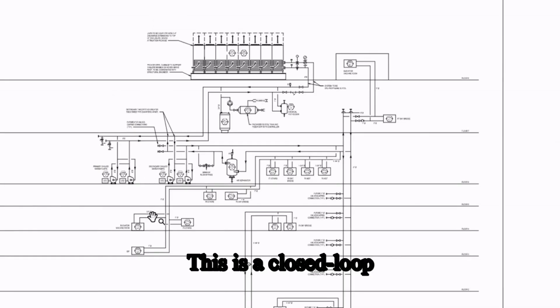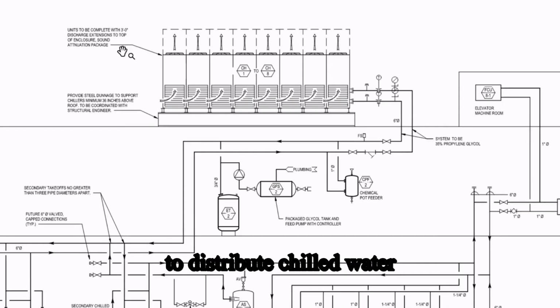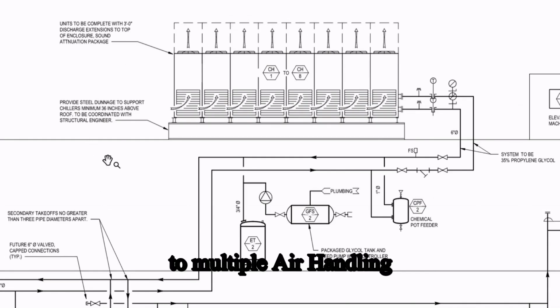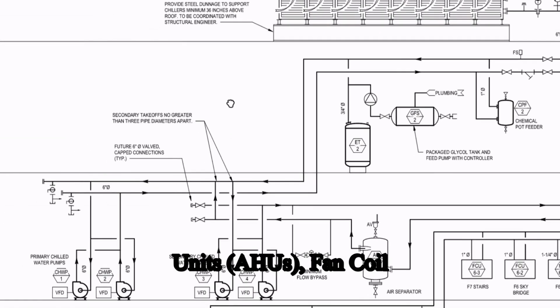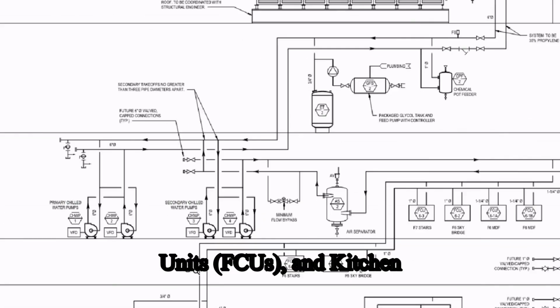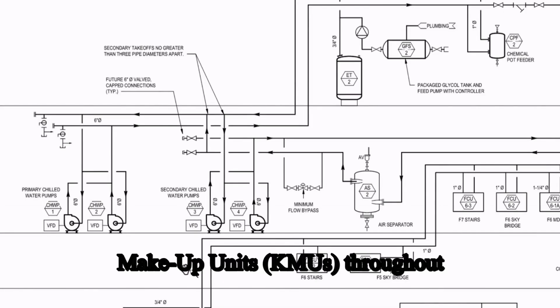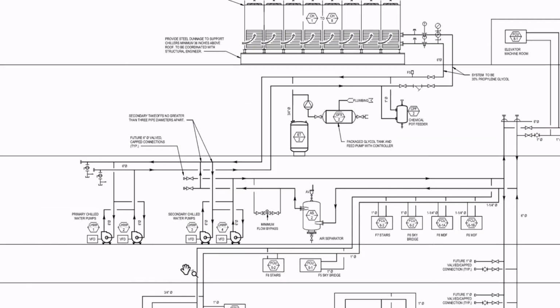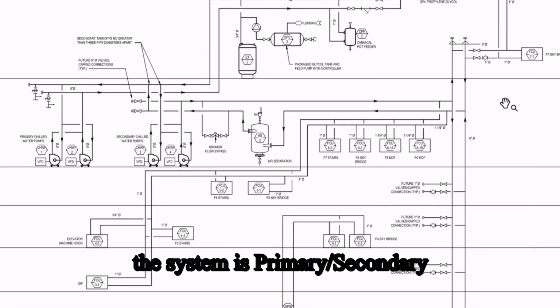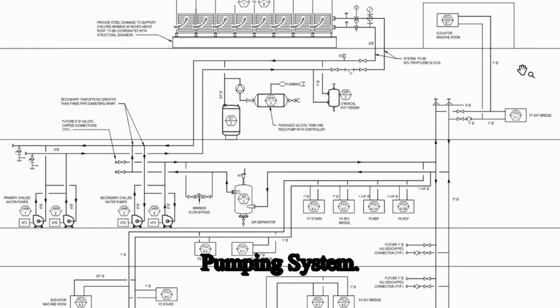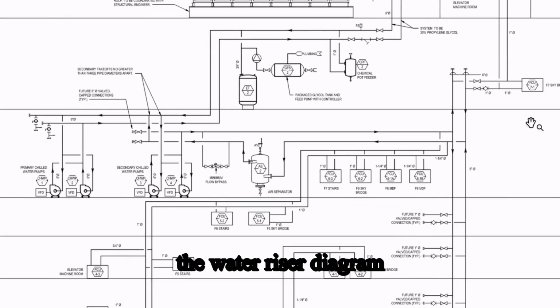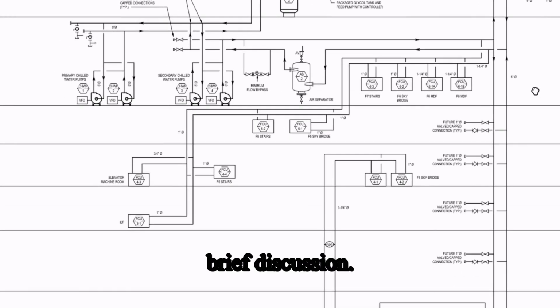This is a closed-loop chilled water system designed to distribute chilled water to multiple air handling units, AHUs, fan coil units, FCUs, and kitchen makeup units, KMUs, throughout the building. The piping arrangement for the system is a primary-secondary pumping system. We will go through the water riser diagram in detail in this brief discussion.